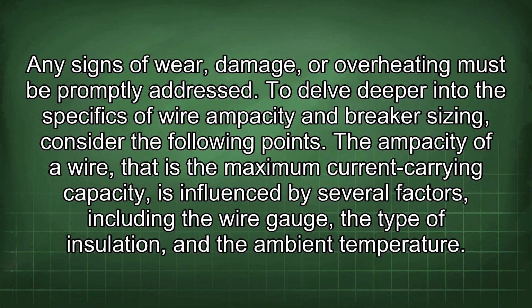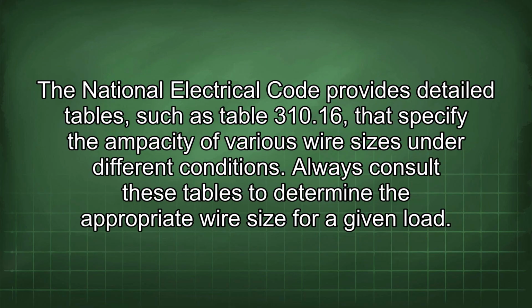The ampacity of a wire, that is the maximum current carrying capacity, is influenced by several factors, including the wire gauge, the type of insulation, and the ambient temperature. The National Electrical Code provides detailed tables, such as Table 310.16, that specify the ampacity of various wire sizes under different conditions. Always consult these tables to determine the appropriate wire size for a given load.